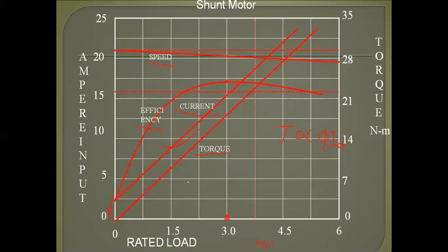For instance, if twice full load torque is required at start, the shunt motor will draw twice full load current, since torque is directly proportional to the armature current, but a series motor would draw only approximately 1.414 times the full load current, since torque is directly proportional to the square of the current.